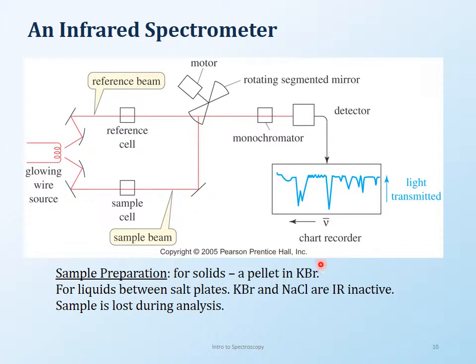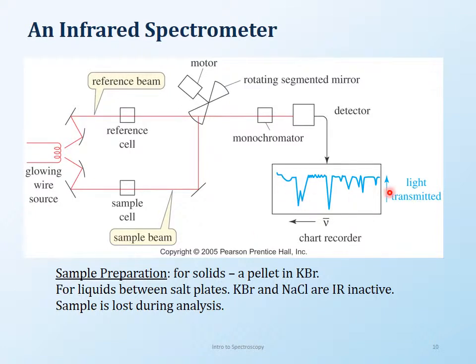This is a schematic of what an IR instrument looks like. You will have a source that gives you infrared radiation. Depending on the instrument, you may have a dual beam or a single beam — with a dual beam you have a reference cell and a sample cell. Most IRs these days are single beam, so you just keep your sample, the IR radiation passes through, goes through a mirror, reaches the detector, and the output is displayed on a computer.